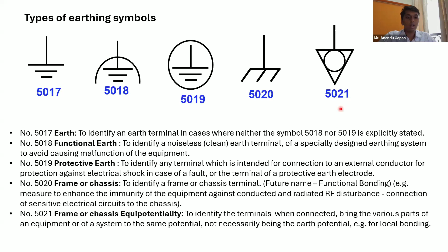This is just some kind of examples on different symbols you can find. Basically, this is for functional earthing. You can find your PE. This is your protective earth, and this is your functional earth. So basically, different kinds of pictures, examples for you to know that functional earth and protective earth are not the same. There are some restrictions which apply to functional earth, and it cannot readily be connected to protective earth also.